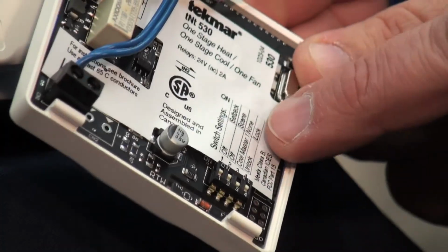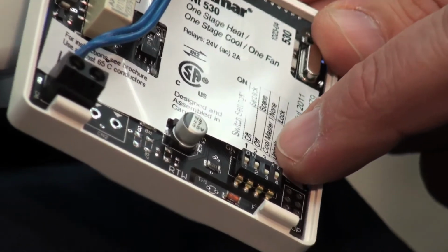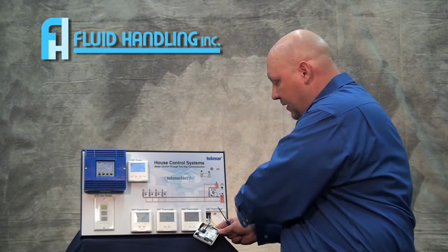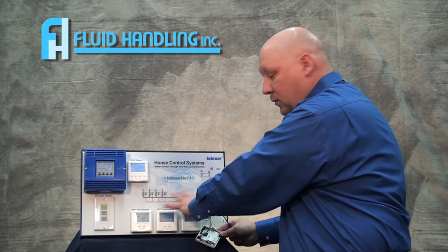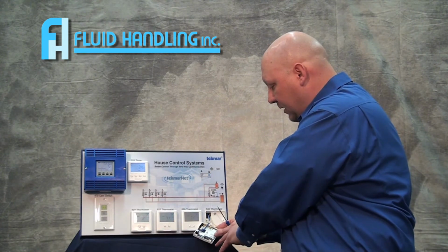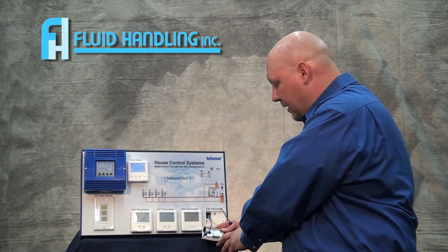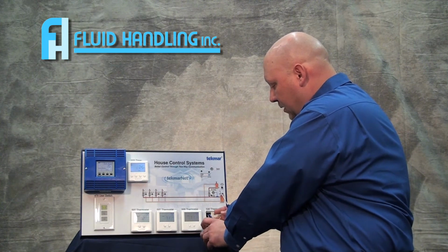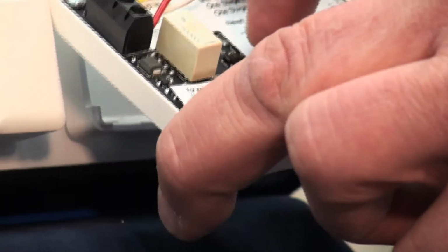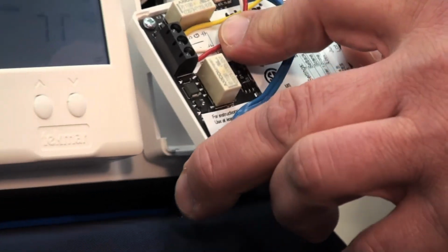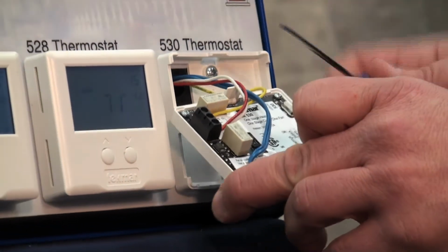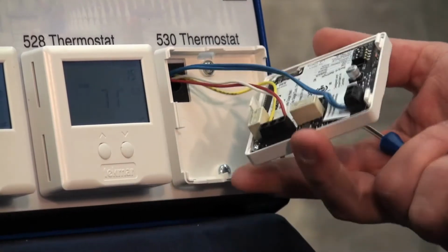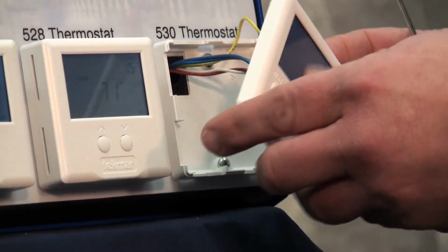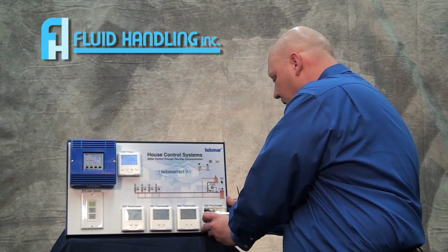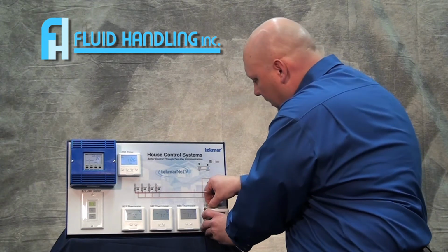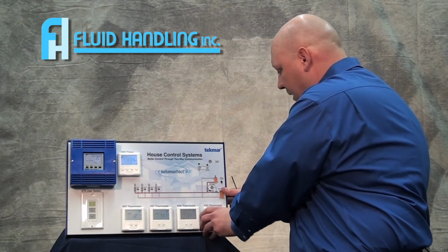You're going to have your setback, your scene, and now you can tell it if it's the cooling master or if it's a standalone by itself with no zones associated with it. You can leave that to none, or you can lock or unlock it. This one on the 530, it's kind of cool because we're controlling the cooling here. So here is your R, your Y, and your G that's going to go to your air handling unit for your air conditioning. So that is our 530 stat. And you have the same sequence for putting it back on.